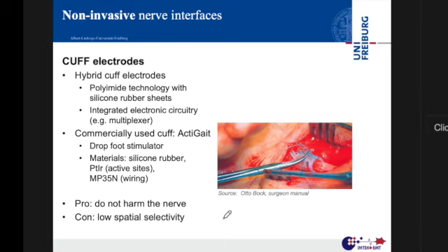Then you have the flat interface nerve electrode, short FINE, which we may hear about because it's a very famous device. And this is like a cuff electrode, but it has a defined shape, so it's already flat and not round like the nerve. So if you implant it on a round nerve, the nerve will be pushed together and will become flat. And the idea of this is that you increase the neural selectivity. So you still have 4 contacts, for example, but since you're pressing the nerve together, these 150 fibers are distributed and maybe grouped, right? That makes sense? Yes, no, maybe? Yes.